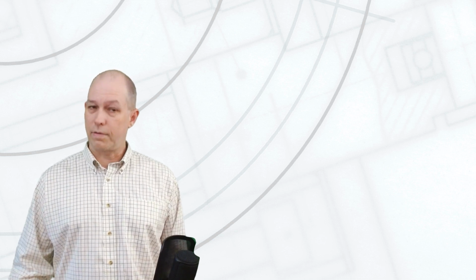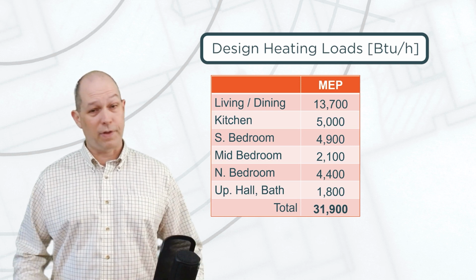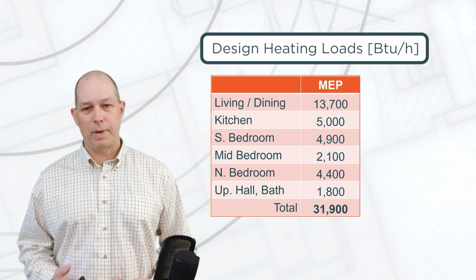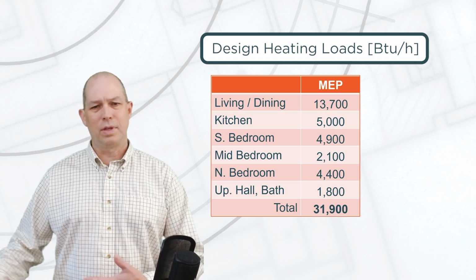And as part of the ratings, we need to review that load calcs were performed. So we got load calcs from the engineer, from the designer, room by room load calcs using a Manual J software. Fantastic. I think this is a very reasonable breakdown of loads. These were 3-bedroom duplexes, really modest. You know, they didn't put closets in separately or the powder room with no exterior walls.